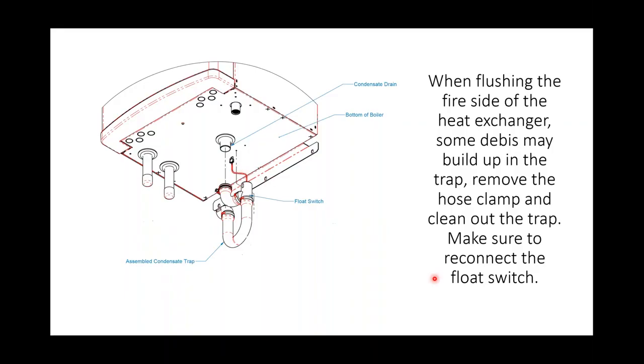One thing, we want to make sure that we reconnect the float switch, or it will not allow the unit to fire. That float switch is just making sure that the trap's not blocked. If it is blocked or fills with water, it'll shut the boiler down. Acts kind of like a wet switch for my scorched air guys out there.